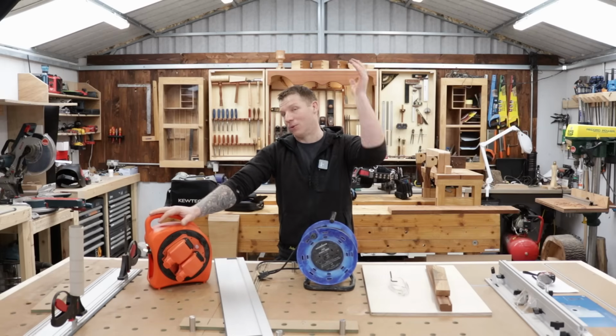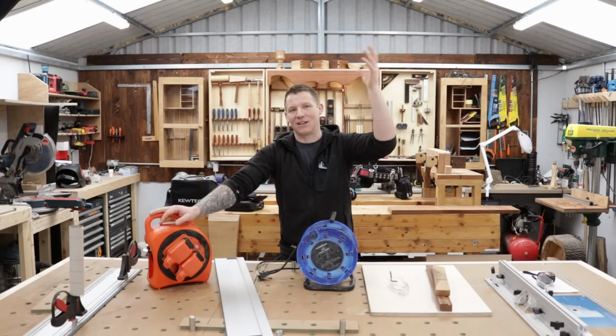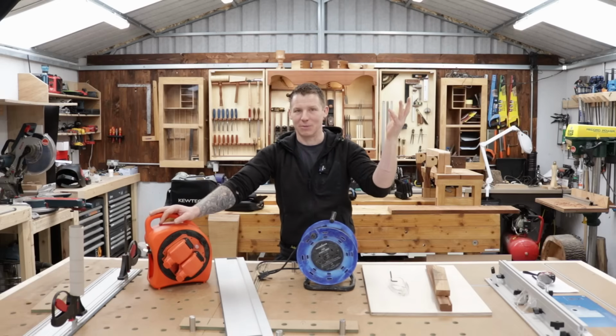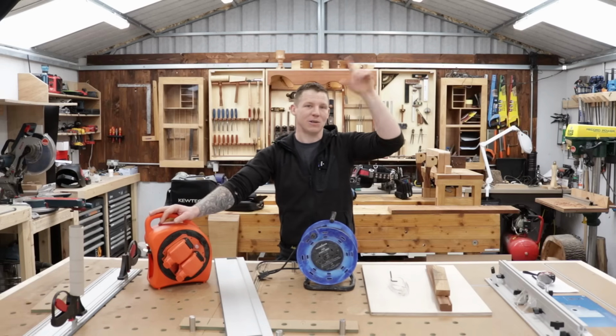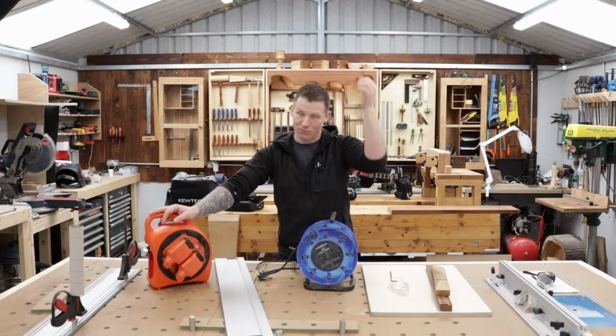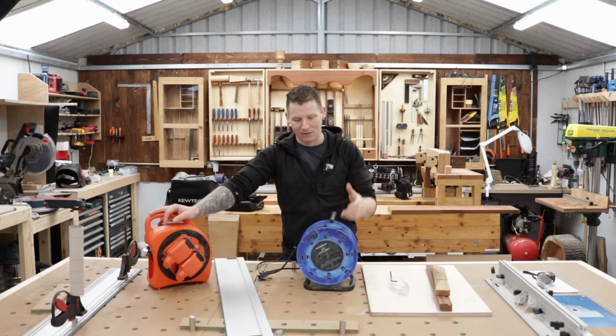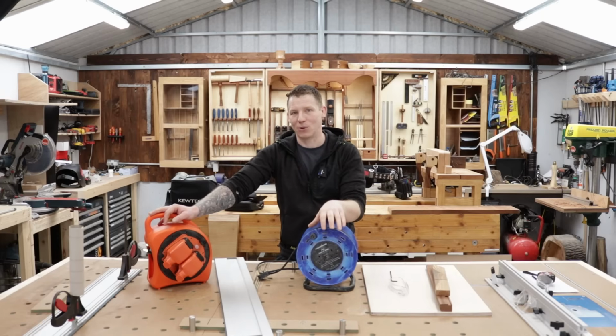You shouldn't use them either, whether you have overhead extension leads that recoil up. I don't recommend them either, because again, you've added 10-20 meters to your circuit. You have a coil that can turn into a heating coil. You're not fully unrolling that coil. So be very careful with these things. They can be quite dangerous.